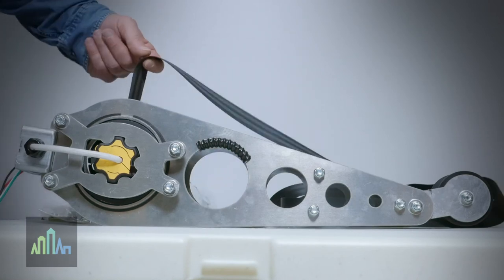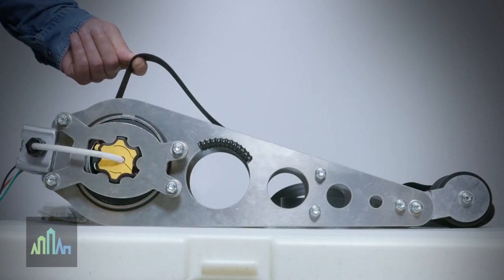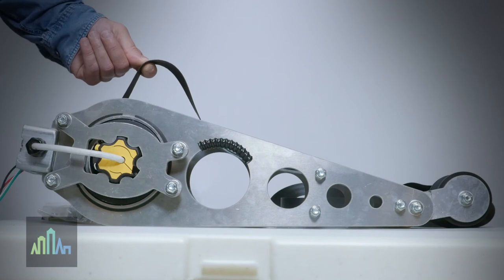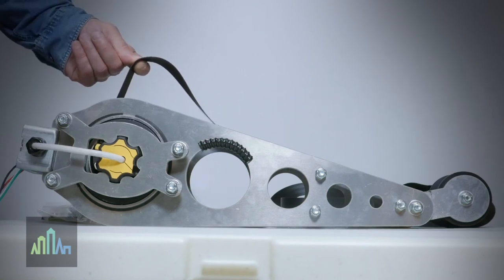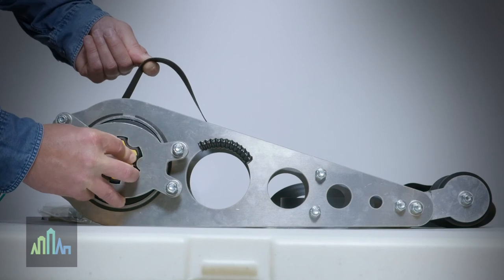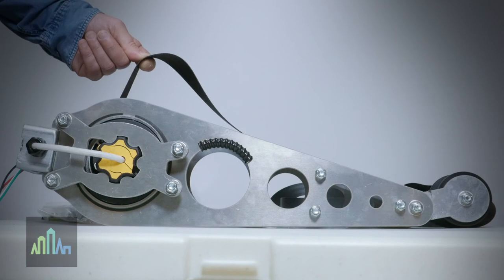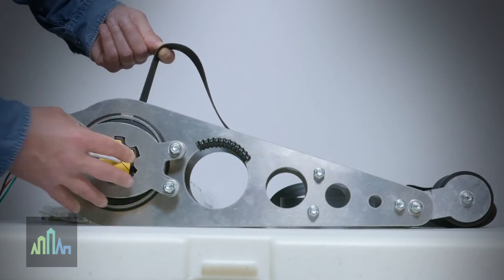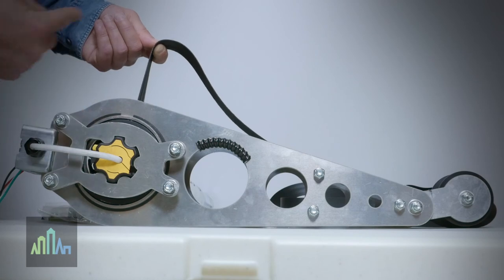So now what I'm going to do is figure out which one of these limit switches. So I just set the yellow one. So now it will not spin in the counterclockwise direction. So that is going to be the down limit switch. So I'm going to get it back to the 12 o'clock position and then I'm going to set it. So now it will not allow you to spin it clockwise.